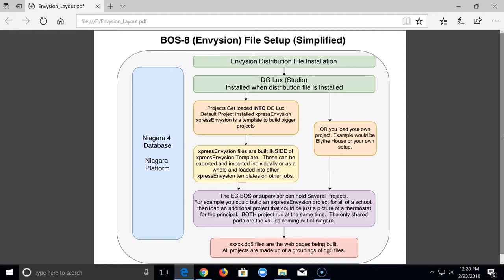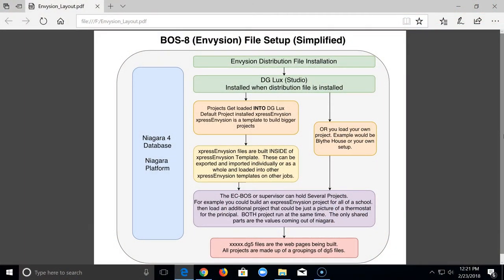The only thing that's shared is the database. If you've got five projects in DG Lux, they're all referencing the same Niagara 4 database — you're just giving them different links. So you can build a project for an energy manager who only wants to see power monitoring. They click around and only see power monitoring — they never get into the HVAC side, only that one project. The DG5 files are basically HTML files that build what you're seeing when you pull up a project.